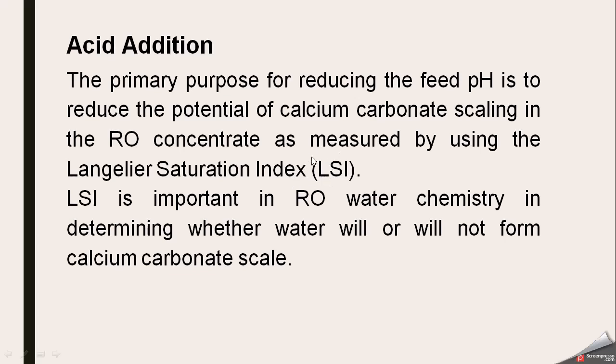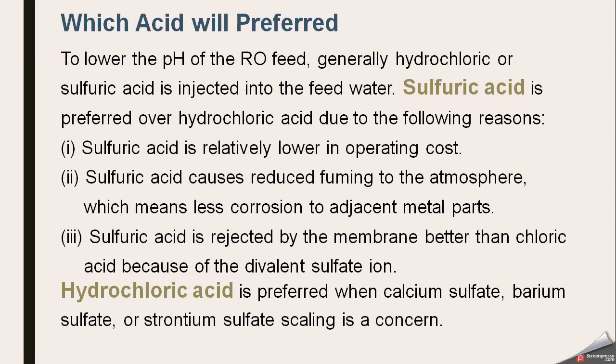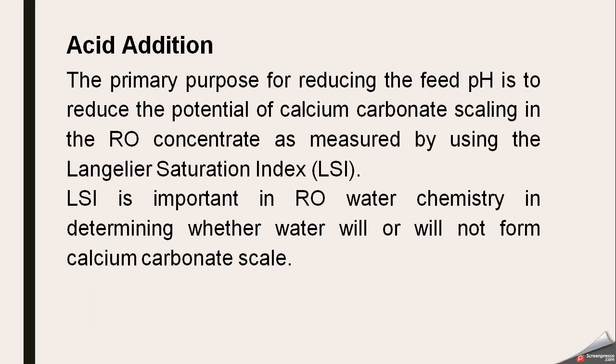In this LSI index, we measure it using different parameters, which include pH, pH of saturation, calcium, and water solubility, and then it tells us whether this water will form scale, or it will be corrosive, or it will be balanced. So this is a very important index in water chemistry for determining whether water will or will not form calcium carbonate scale or any other type of scale.